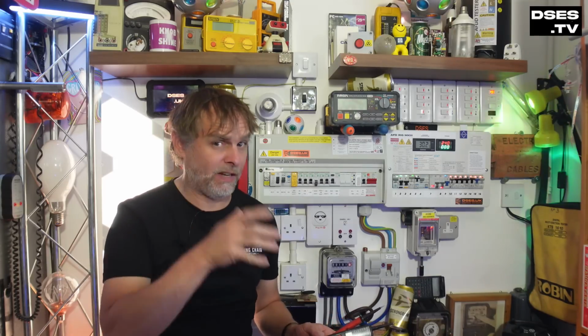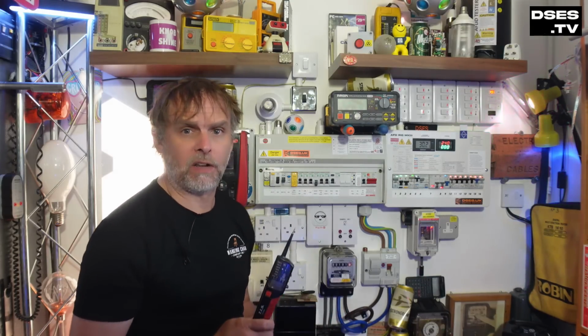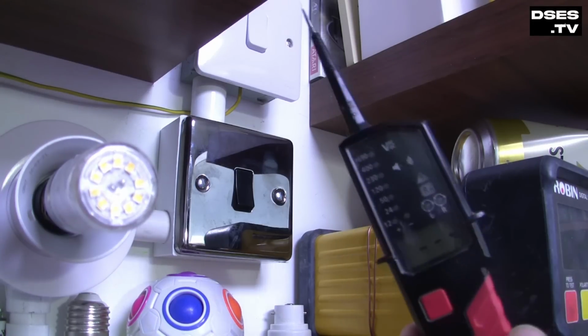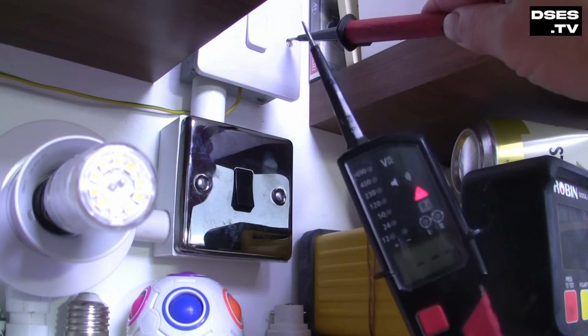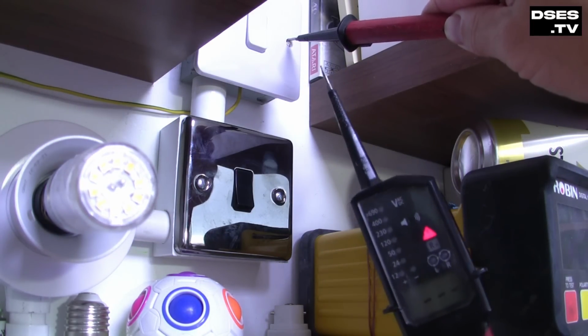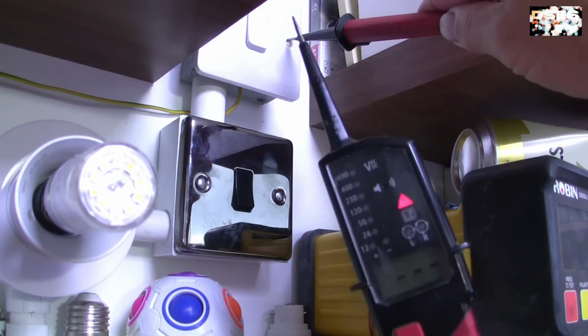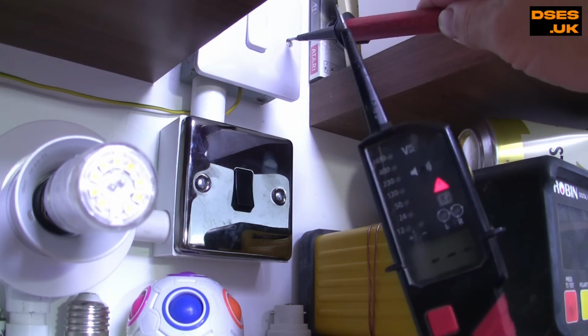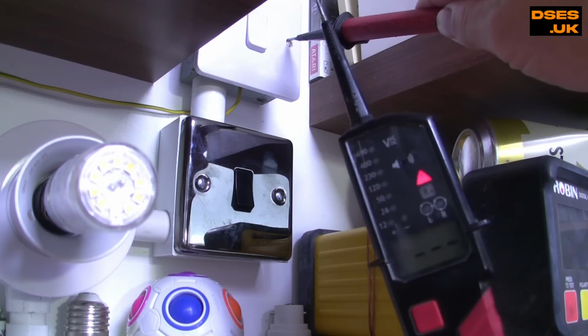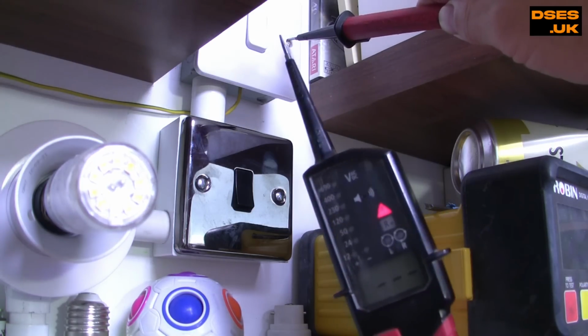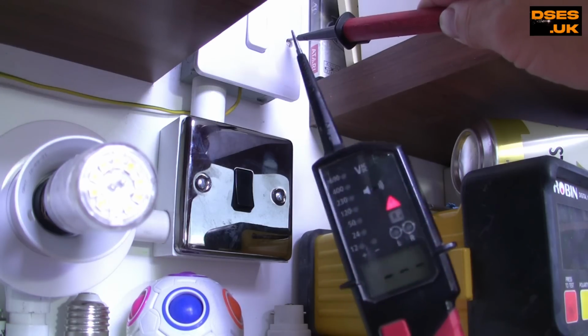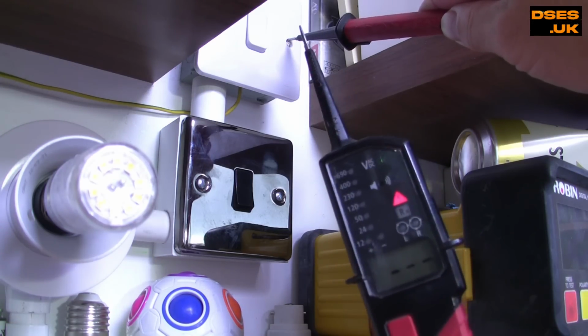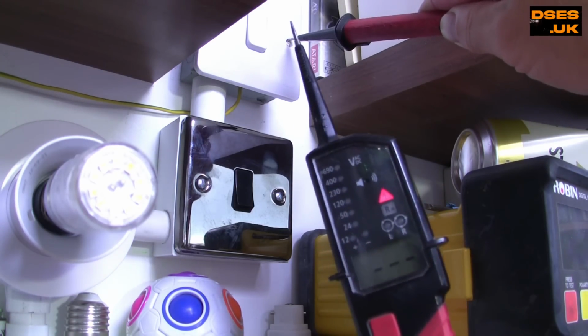I'm not going to say reason 2 because many such devices lack this feature. However, my 845 here will give a warning of voltage presence with just one probe touching. Observe: with just one probe contacting the metalwork, there's already an audible indication and a warning light giving me a heads up that something is live on these screws. This thing can detect voltage very sensitively. A multimeter with one probe connected might give all sorts on the display, maybe something useful, maybe complete nonsense, but at least the 845 is telling me to proceed with caution.